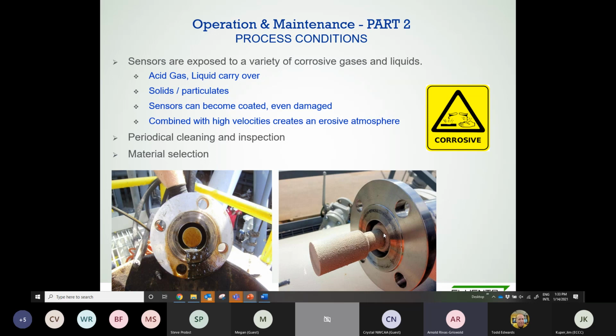Normally, the sensor rod would be stainless steel for the most part, and the tip is made of titanium grade 2. But if you have an application with a very sour service, then you may want to consider other alloys, Inconel, Hastelloy, et cetera, or maybe duplex could be an option. But of course, that increases the price of the sensor. So that's something we want to address with the customer early on, so they can really assess the risk and benefits of getting those alloys.